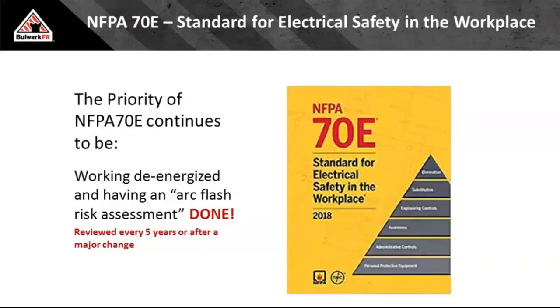I think it's 35 different times within the document that it directly addresses the hierarchy of safety. But what is the priority of NFPA 70E? Well, the biggest priority for this is not arc flash. It's don't get shocked. It is work de-energized. Remove the energy from the equipment so that you can doff all your PPE, work on it easily, more quickly, put it all back together, re-energize it, and get on with your day. So the biggest part of 70E is working de-energized as often as it is feasible.